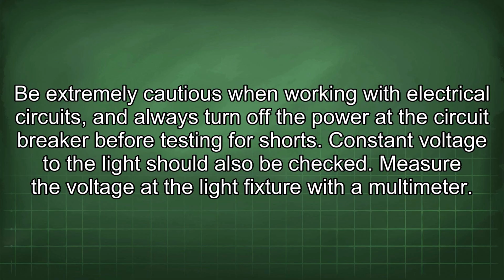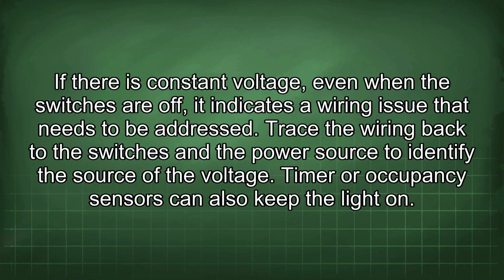Measure the voltage at the light fixture with a multimeter. If there is constant voltage, even when the switches are off, it indicates a wiring issue that needs to be addressed. Trace the wiring back to the switches and the power source to identify the source of the voltage.